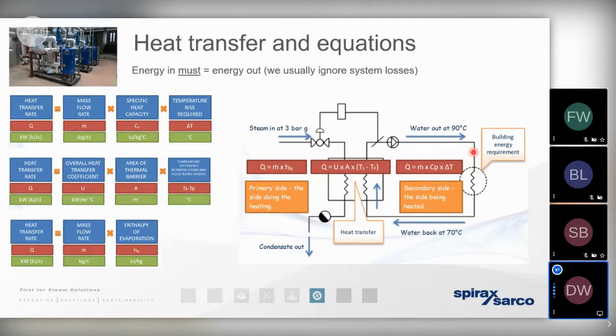Now, what we need to remember here is that if we go back to first principles with thermodynamics, we know that energy in must equal energy out. It cannot be created. So what that basically means is if we've calculated the Q value at any point of the process using the equations you can see here towards the left-hand side of the screen, well, we can simply carry the Q value across from one point to another point. For example, if we've calculated how much energy the process needs, by definition, we've also calculated how much energy needs to be present in the steam on the primary side.